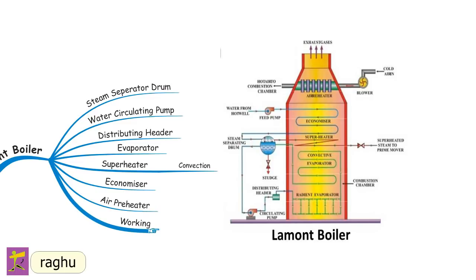In the working of the La Mont boiler, feed water passes through the economizer to the drum, from which it is drawn by the circulation pump. The pump delivers the feed water to the tube evaporating section. The circulating water is about eight to ten times the steam evaporated. Steam in the drum is a mixture of steam and water, which is drawn through a convection superheater, and the superheated steam is supplied to the prime mover. The working pressure is 170 bar with capacity up to 50,000 kg/hr at 500°C.